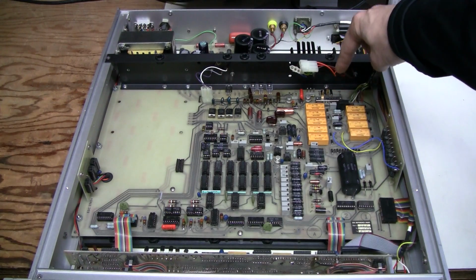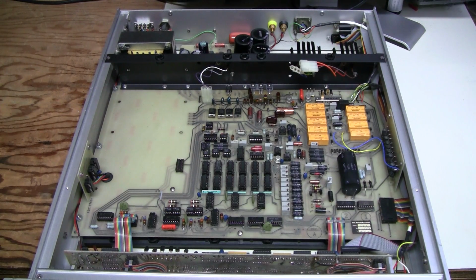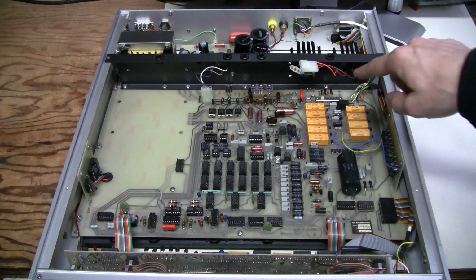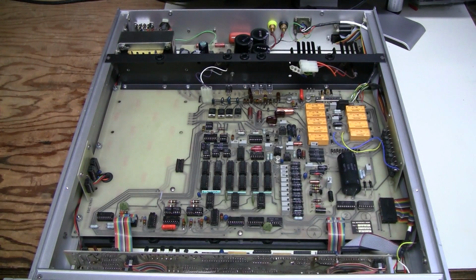for the voltage limit in the current mode. It is set to the maximum now, which means the voltage on the output terminals is limited to 100 volts in the current mode and can reach up to 150 volts if the circuit is open, which is the limit of the power supply. And in the minimum setting, the voltage is limited to about 1.2 volts, and for the open circuit it is limited to about 11 volts or so.